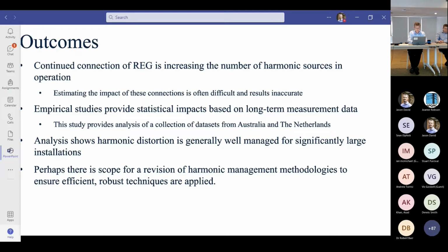That would go some way to describing that slow downward trend that happens over a number of years, all the way up to commissioning of the installation. But the big outcome is that we're not seeing this linear increase of harmonic distortion, even though we are seeing a substantial increase of harmonic sources being connected on the network.